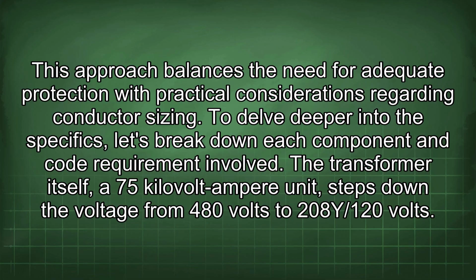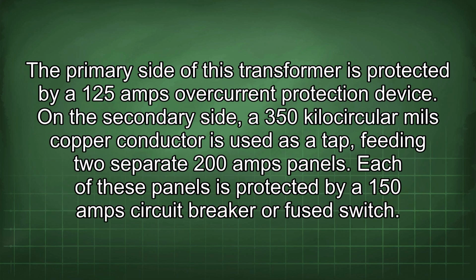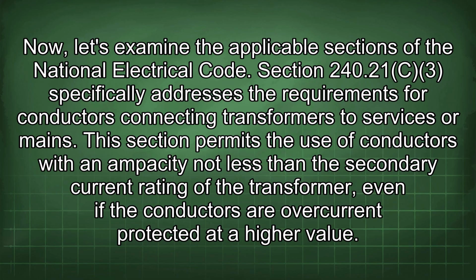The transformer itself, a 75 kVA unit, steps down the voltage from 480 volts to 208Y/120 volts. The primary side of this transformer is protected by a 125 amp overcurrent protection device. On the secondary side, a 350 kcmil copper conductor is used as a tap, feeding two separate 200 amp panels. Each of these panels is protected by a 150 amp circuit breaker or fuse switch. Now let's examine the applicable sections of the National Electrical Code.